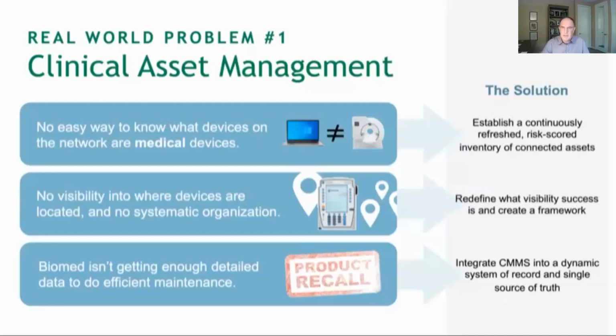Number three, and Tom touched on this, Biomed groups care a lot about understanding the device at the serial number level, and automatically when they get information from a lot of monitoring systems, you just know stuff like make, model, high-level information. And then the maintenance management system assigns a unique asset ID to every medical device, but often Biomed doesn't know the serial number information. So in a scenario where you've got a product recall that's covering a certain amount of devices, and you can link that to the serial number, when you know the serial number itself, you're able to then link the information required on a per device level, exactly to the device and where it is.